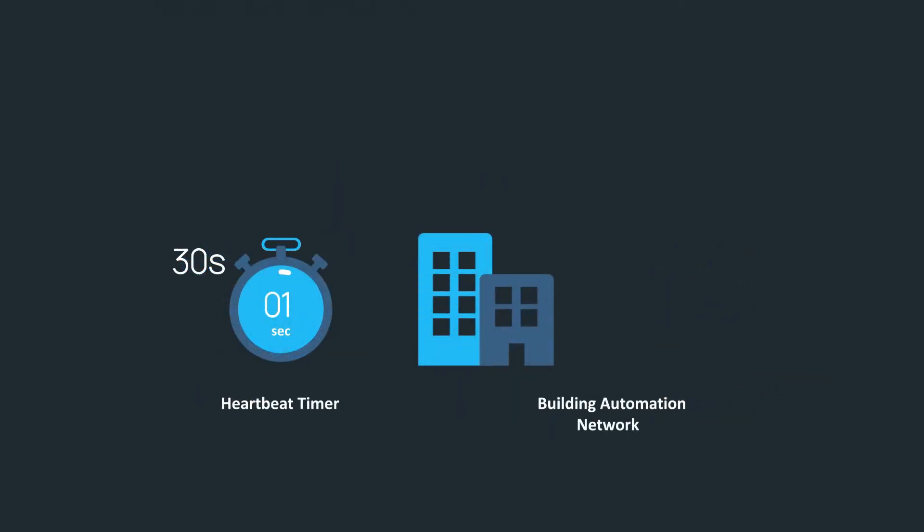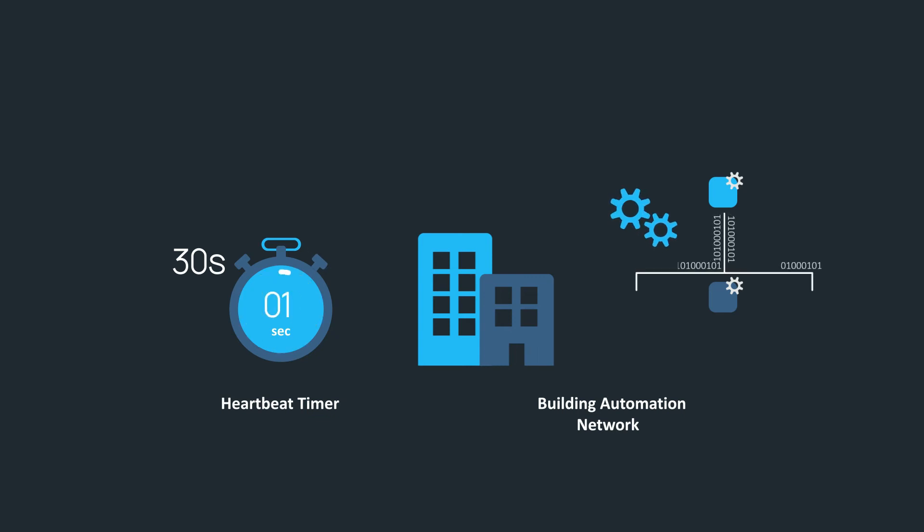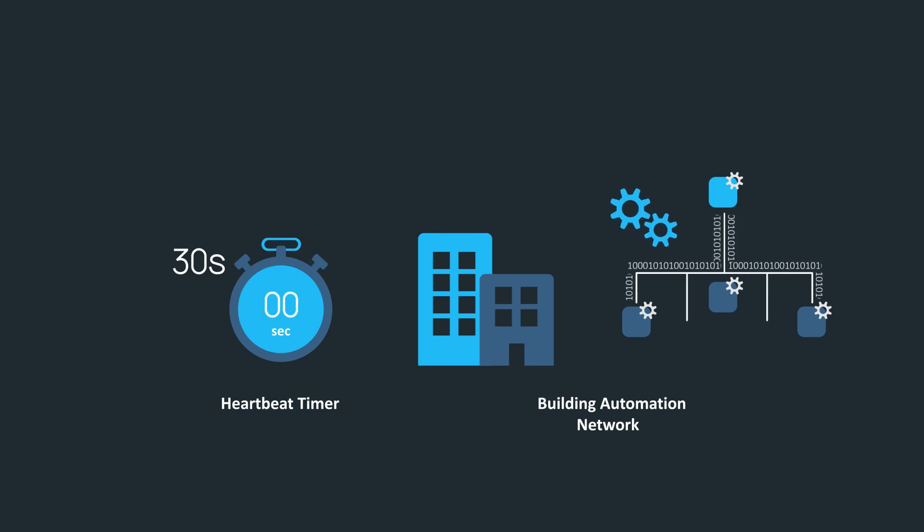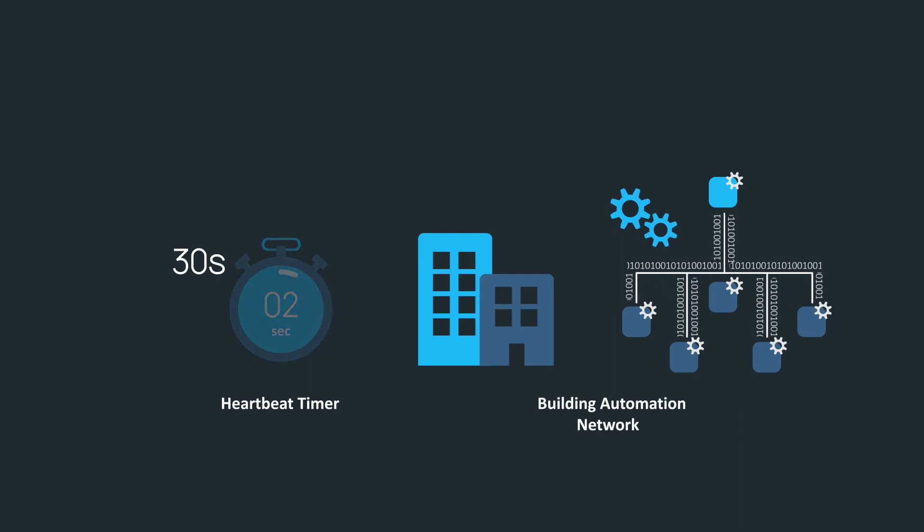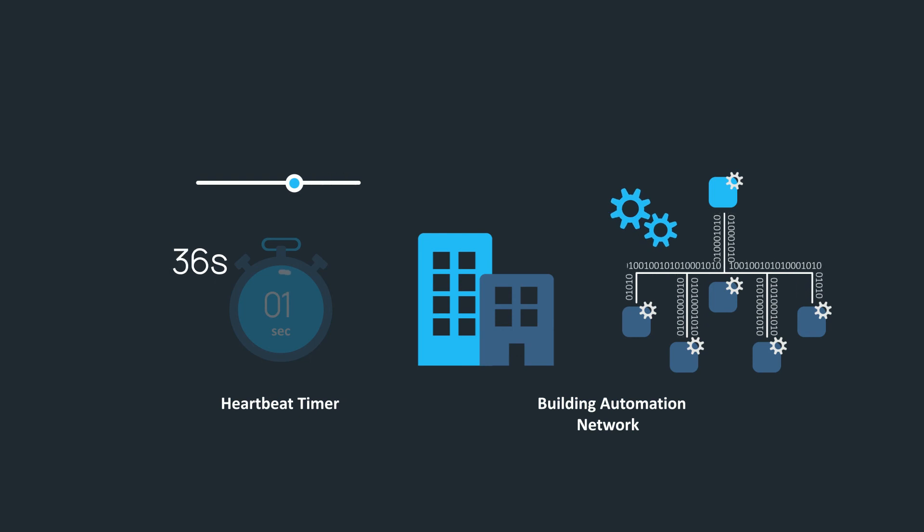We should note the speed in which data is transferred between the BAS and the Express Optimization Controller is subject to the number of devices on the network and overall network traffic. As a result, the specified value of the heartbeat timer may need to vary, so it should be user-adjustable.